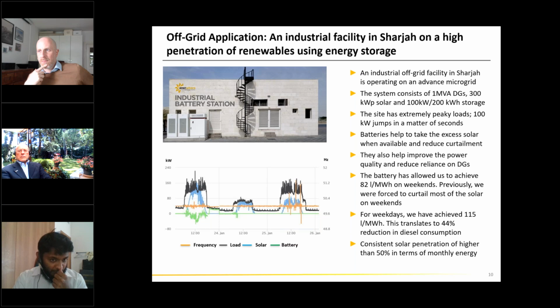On the 23rd of January, with the batteries operating, you can see the system frequency, the orange line, is quite stable, because the batteries are soaking up the extra solar despite all that peakiness on both the solar and the loads, maintaining the frequency quite strongly. On the 26th of January, we had a problem with the batteries, so they were out of functioning. We had to curtail the solar down quite a bit to keep it a few tens of kilowatts below the load to avoid problems, and you can see the system frequency is completely off the charts, fluctuating between 49 and 51. This is a nice example of the advantage batteries bring to a system, especially an off-grid system with very high variations or fluctuations.